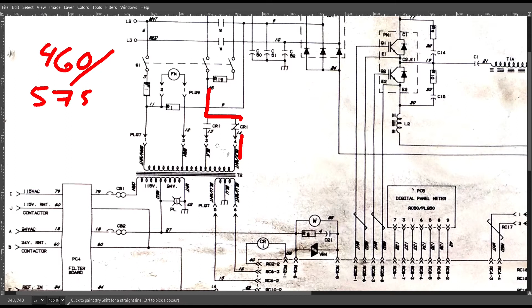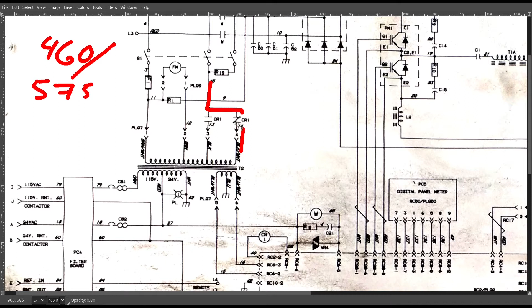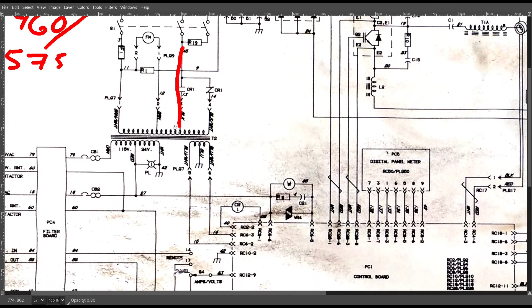If on power on it does this, but you were only running 460 volts, then the control board detects this condition, and then, as I said, it energizes CR1, which means this contact opens and the other one closes. So then you're feeding the transformer from the shorter winding, which means you'll get the proper 24 volts.